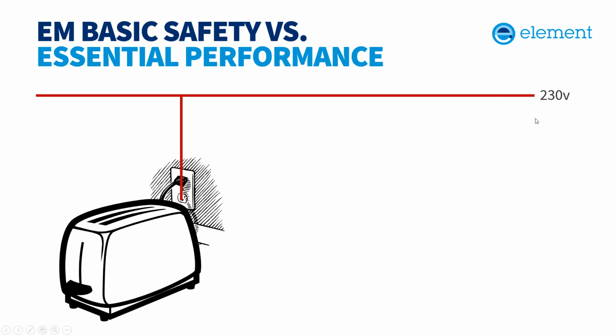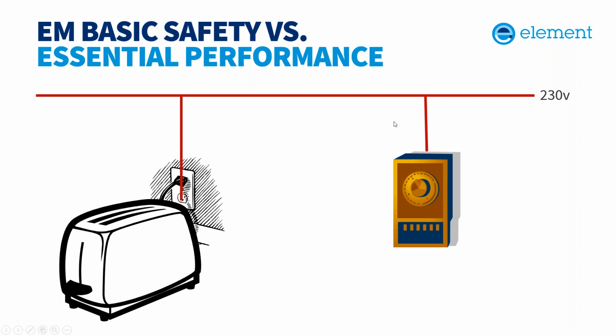So here's a real-life example for a non-medical device. This is something that actually happened over in Denmark a few years back. A toaster was plugged into the AC mains, and toasters used to be basically just a giant resistor, but now they have digital logic in there. It was plugged in the mains, and a nearby thermostat kicked on. The thermostat caused transients on the mains, and the toaster saw that as a signal to be turned on, and it powered on and ended up causing a house fire. So there, the essential performance of the toaster might be considered making toast, being able to toast bread, but it did not meet basic safety, causing a fire there. So you've got, what's it supposed to be doing and making sure it doesn't actually cause harm.